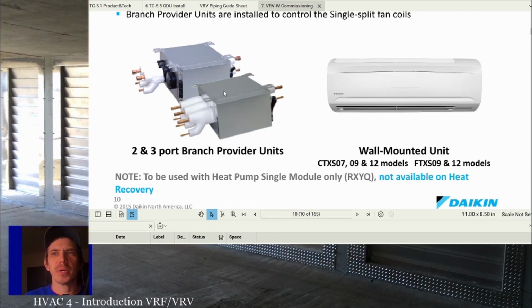They actually separate the liquid from the gas inside their branch boxes. Kind of neat. I remember reading about it the first time a few years ago, and it's an extremely neat idea. So it's something to look into if you ever do Mitsubishi VRF. I've never actually installed it, seen it operate, or know if it does a good job, but it's a cool way of solving the problem of having to run that extra pipe everywhere like you do with heat recovery. But anyway, back away from that digression.